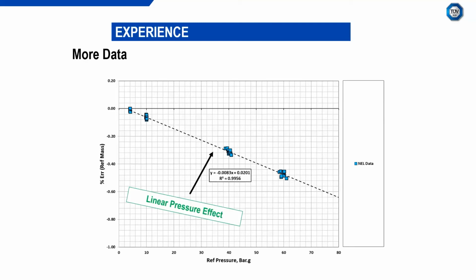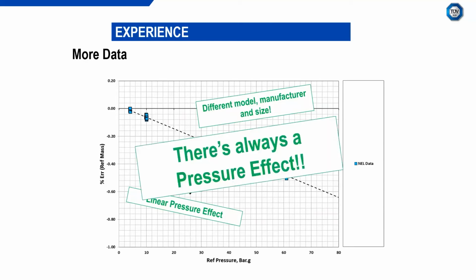Just want to stress the point that pretty much all Coriolis meters are affected by pressure to some degree. It might be positive, it might be negative in terms of the effect. So it might cause an overread as well, as opposed to an underread. But there more than likely will be a pressure effect. It just depends on the significance of it. So, as I say here, there's pretty much always a pressure effect for Coriolis meters.